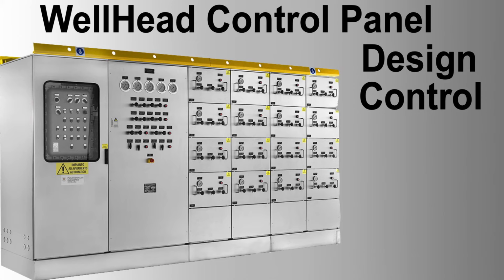Flow control loop. Sensor: flow meter, range 0 to 5,000 BPD, accuracy 1%. Actuator: flow control valve, 4 to 20 milliamps control signal. PLC RTU: PID control algorithm, set point adjustment via HMI SCADA. Feedback: real-time flow rate data to PLC RTU. Alarm: high-low flow rate alarms. Shutdown: ESD if flow rate deviates significantly from set point.